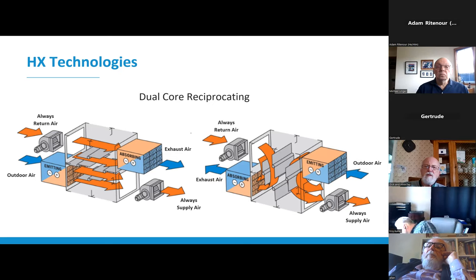Some advantages of this type of heat exchanger technology is that it's self-cleaning. There's no defrost needed down to negative 40 degrees. This type of heat exchanger can get up to 90% sensible recovery in the winter, which makes it a very good piece of technology for cold climates.